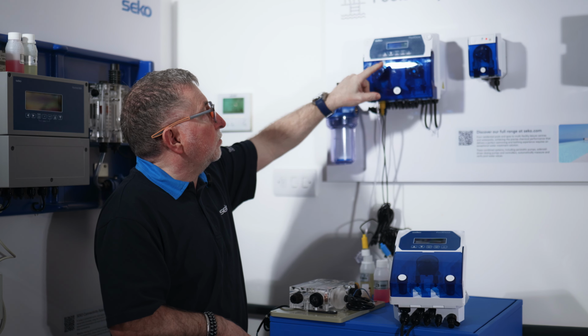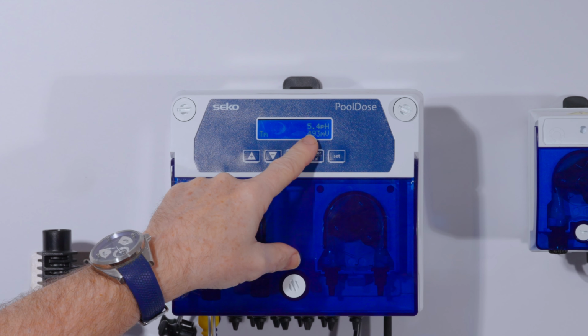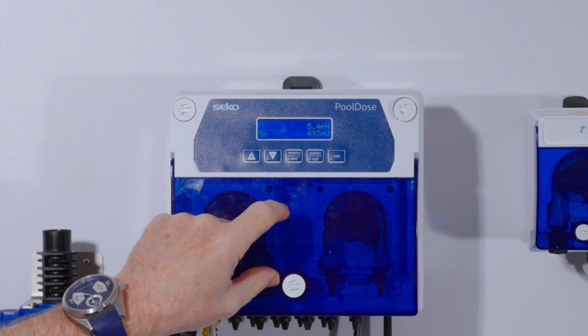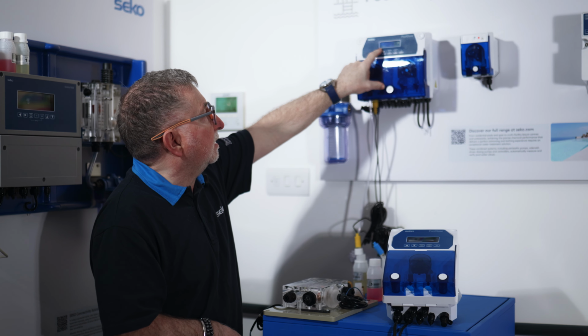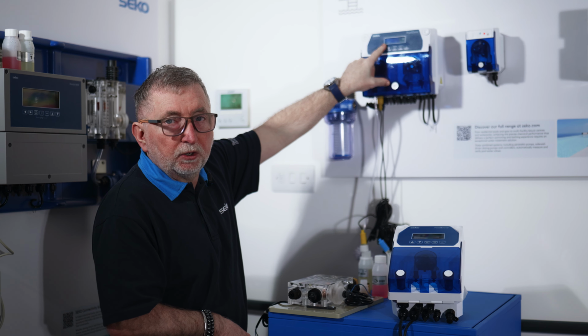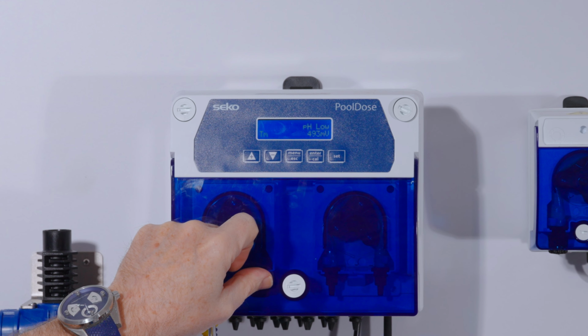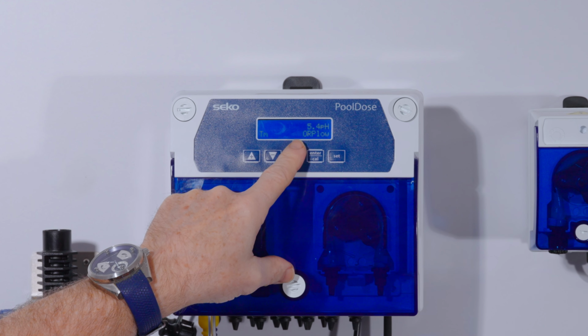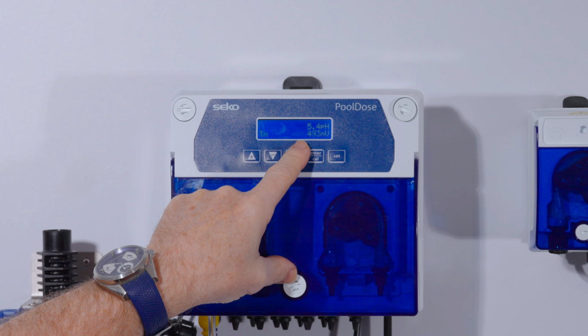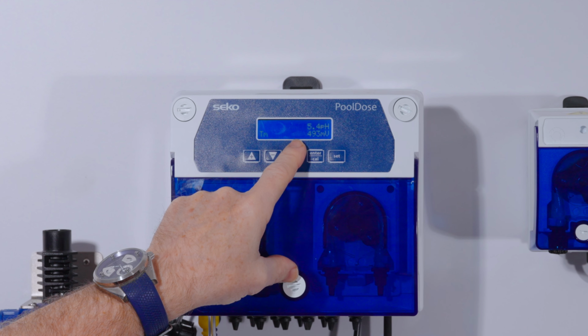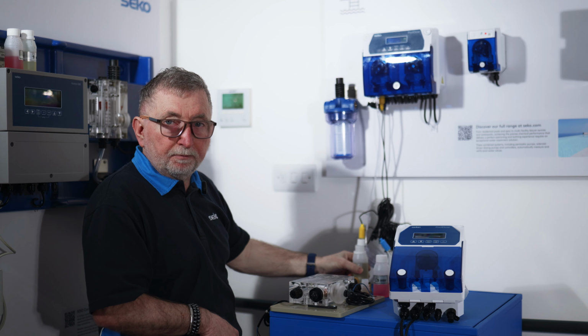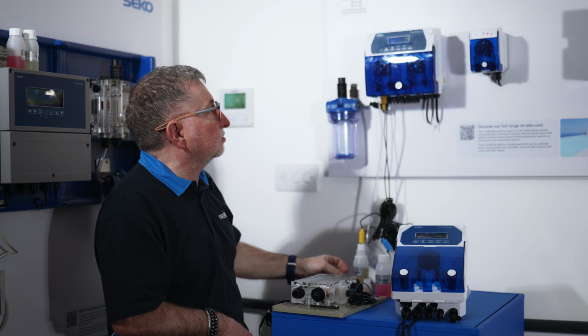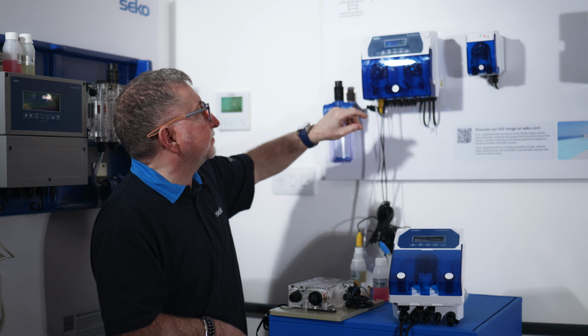On the display itself, we can see we have a reading now of 5.4 for the pH and 493 for the millivolts. We don't have a temperature reading on this particular unit, but if there was one fitted, it would be displayed. You can also see periodically we're getting a low reading for the pH and the ORP because we're currently using buffer solutions to measure this rather than the actual water parameters.